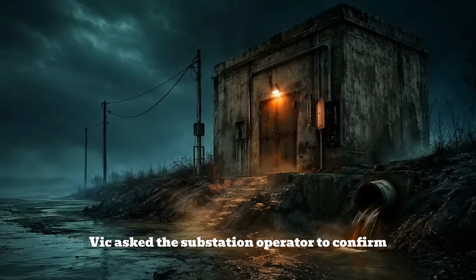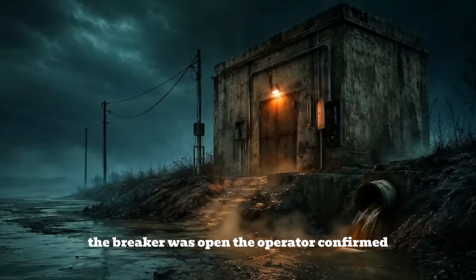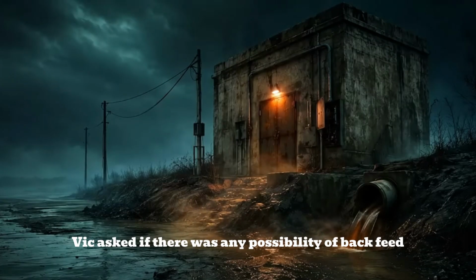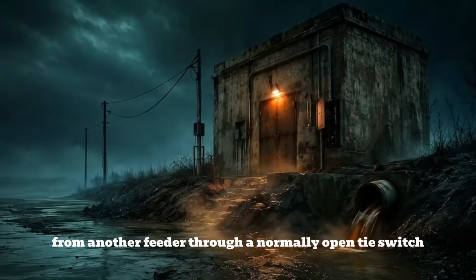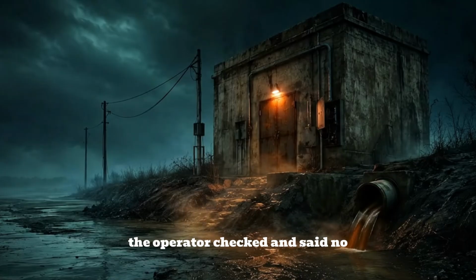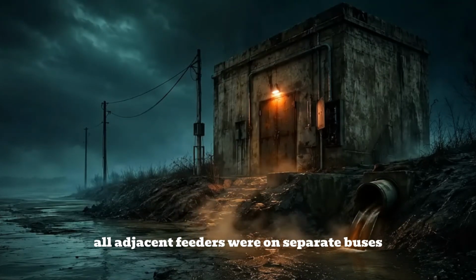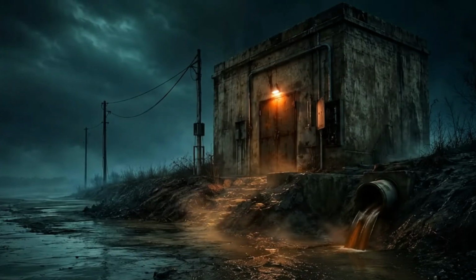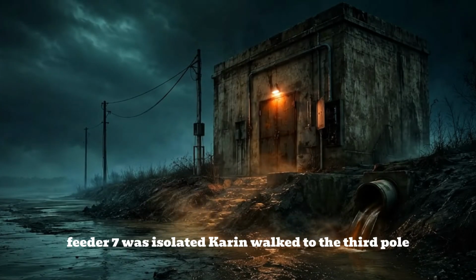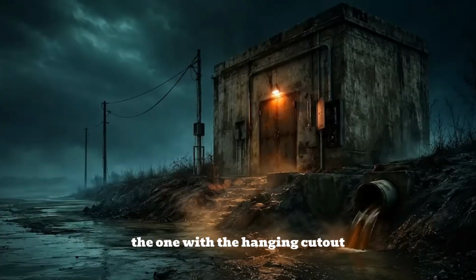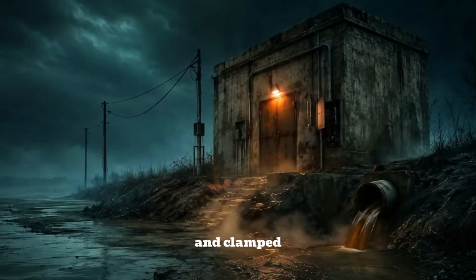Vic asked the substation operator to confirm the breaker was open. The operator confirmed. Vic asked if there was any possibility of backfeed from another feeder through a normally open tie switch. The operator checked and said no, all ties were open. All adjacent feeders were on separate buses. Feeder 7 was isolated.